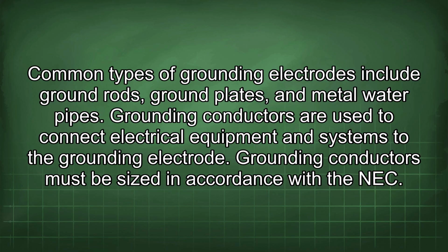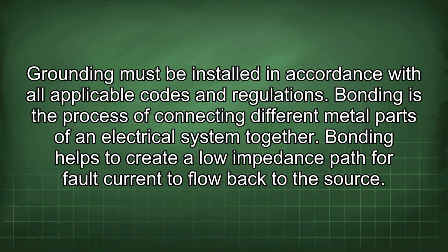Common types of grounding electrodes include ground rods, ground plates, and metal water pipes. Grounding conductors are used to connect electrical equipment and systems to the grounding electrode. Grounding conductors must be sized in accordance with the NEC. Grounding must be installed in accordance with all applicable codes and regulations.